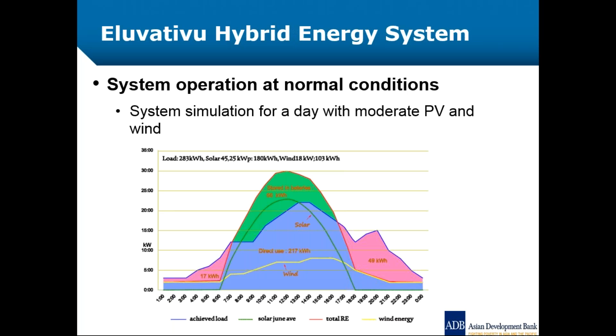The challenges we had were mainly about the load profile common to these islands, which has a morning peak as well as an evening peak. Because of that, the solar or wind can easily ride through during the off-peak, especially at night for wind, and during the day for solar since there isn't much demand. So the excess energy was a challenge, how to utilize it, and whether we required a diesel generator or not. But the outcome was a combination of these options.